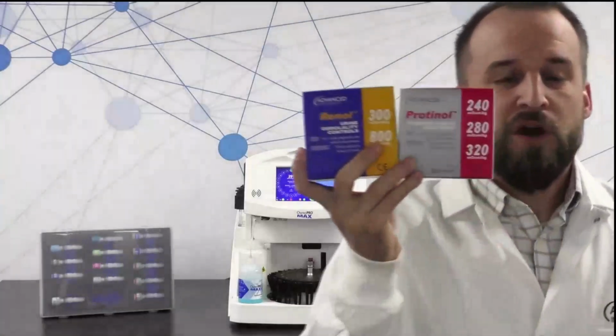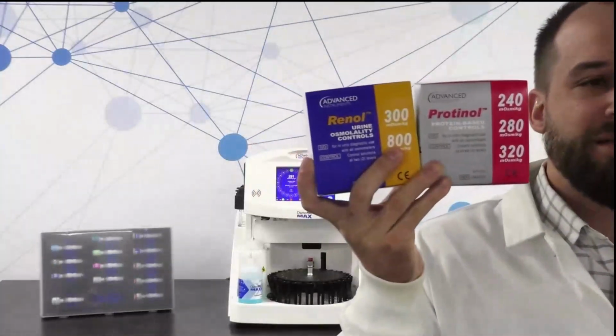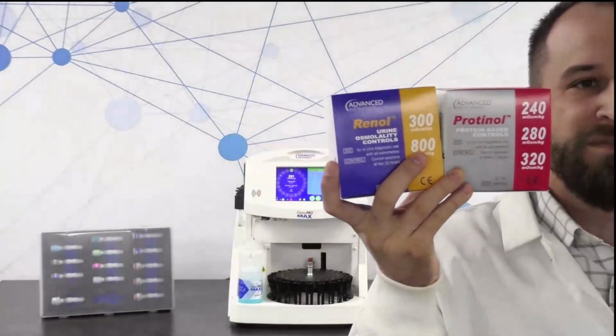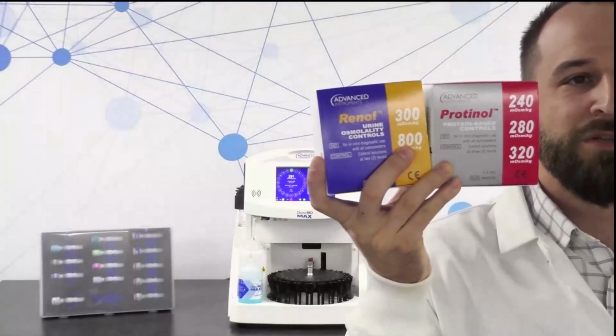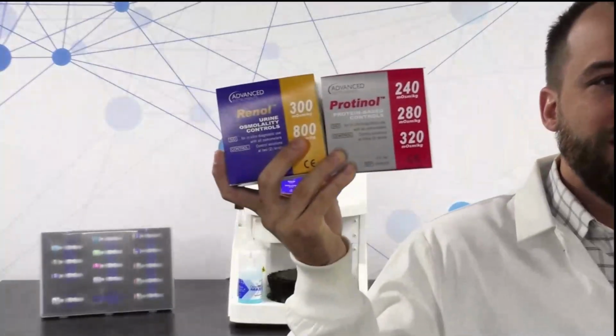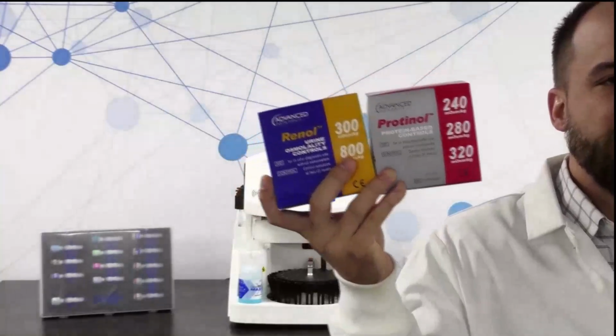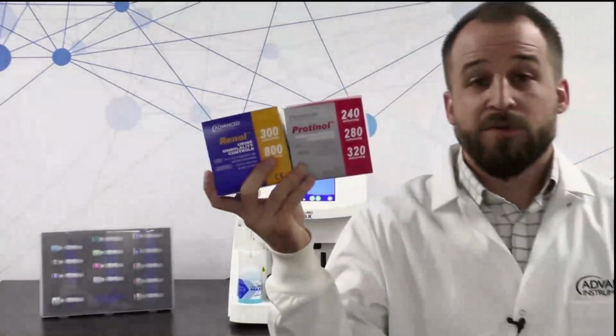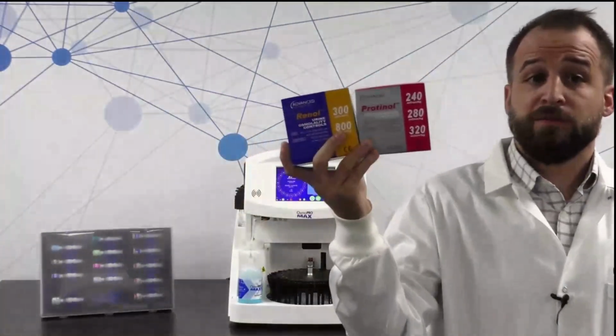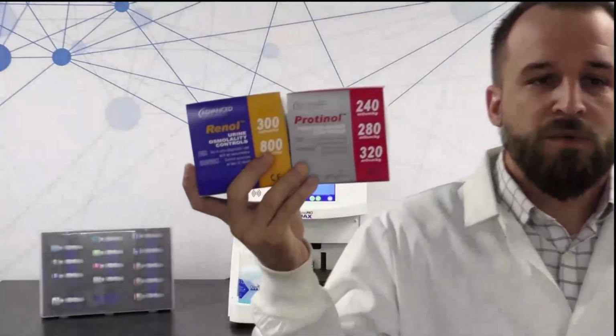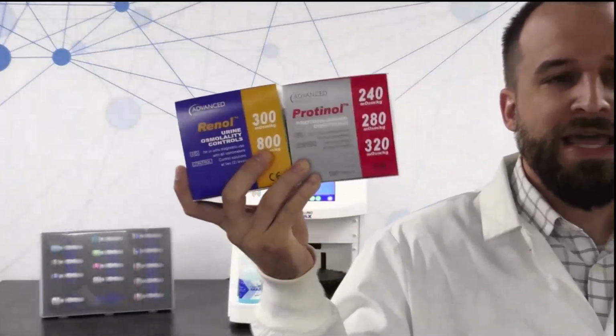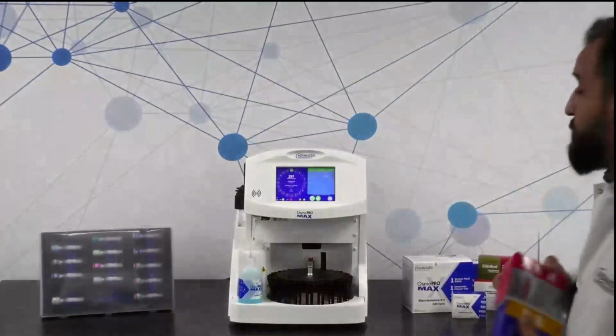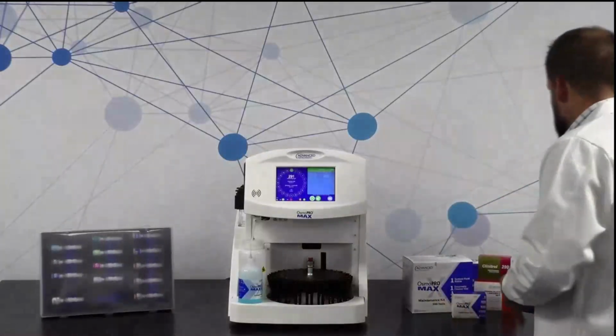So we have Protinol, which is our protein-based matrix, so it's meant to mimic a serum or plasma sample. We've got results from 240 to 320 with 280 right there in the middle. Renol has a much broader range, because as you know, depending on what you're testing urine for, you can get results that are really, really low or really, really high. So for Renol, we have 300 and 800 milliosmol standards for daily QC on those as well.